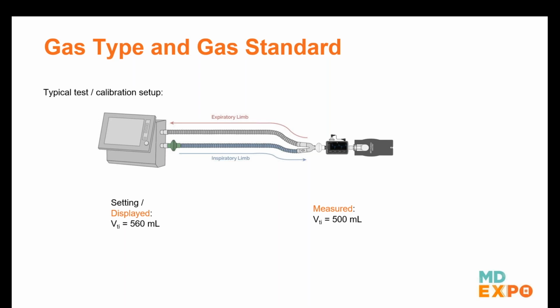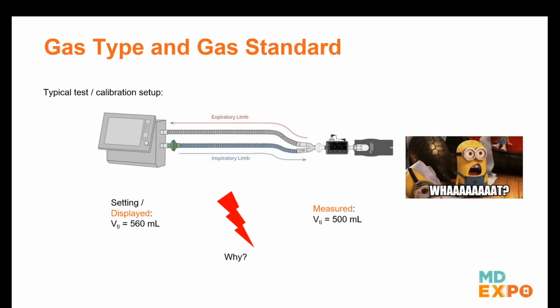So this looks like there's something wrong here. One of these devices is not measuring correctly, right? I'm off by more than 10%, and this is just at one point. What happens if I test over a big range of volumes, right? I'm off by quite a bit here. What's the problem? Do you start troubleshooting now? Do you say the ventilator's no good? Do you say your analyzer needs calibration? What do you do? Try a different analyzer, right? Chances are you're going to get the exact same results though, right?